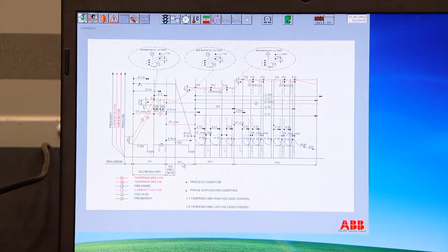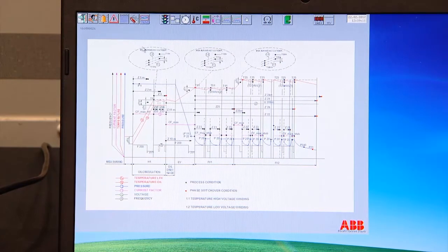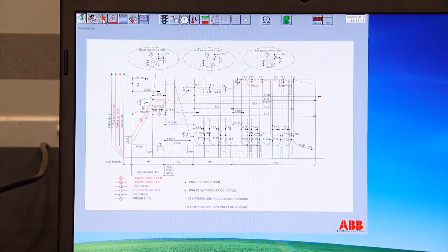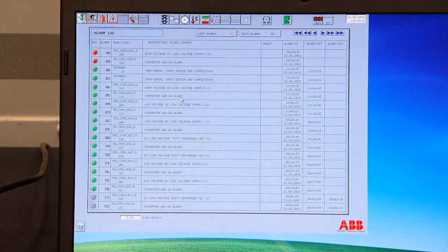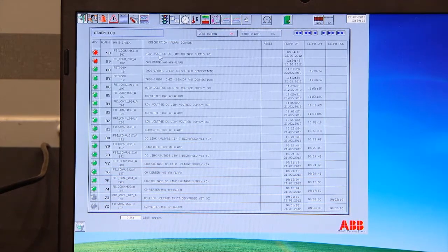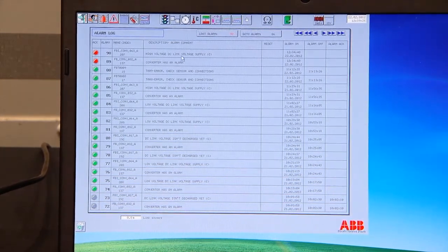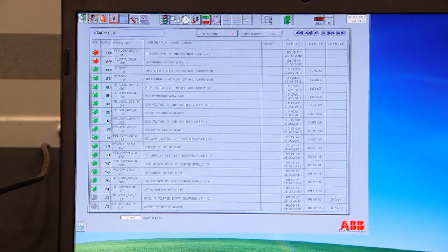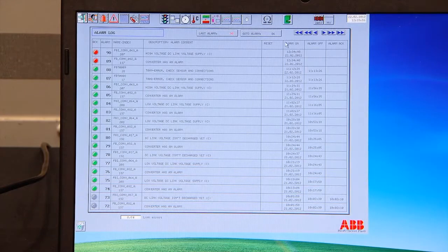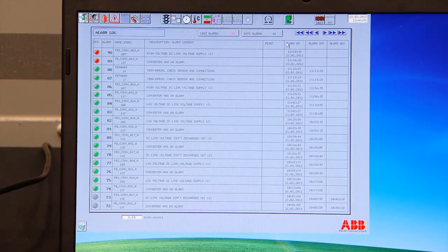Yeah. So the converter stopped for some reason. We get an alarm. It's flashing up on the alarm bell. We click on it and see. We are getting a similar voltage to yesterday, but this time it's high voltage on the DC link. But that was the last alarm we got. Then another voltage reading. I have a voltage sensor measuring this, and that protects the capacitors. It is on the DC side, yes.